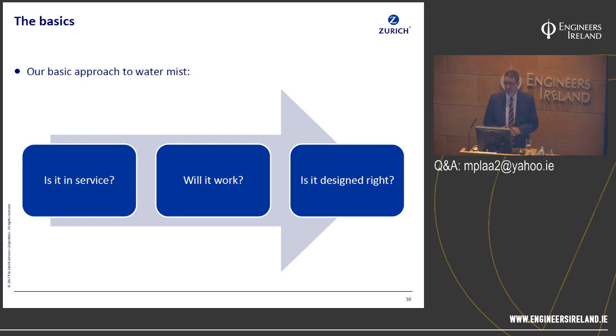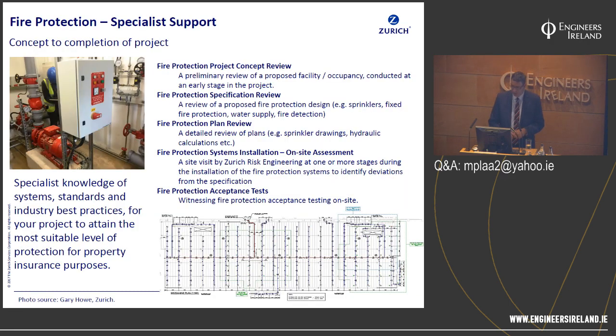And this 3-stage process is really useful to us. It verifies the effectiveness of that system. And we do that by undertaking this 5-step process. So all of the major projects we work on, we undertake this 5-step process for our underwriters. So we go through a detailed design, installation, specification, on-site verification, and checking site plans, hydraulic calculations. That way, if we go through that 5-step process, we can, with confidence at the end of that process, come up with an assessment, analysis, and an opinion of that risk.